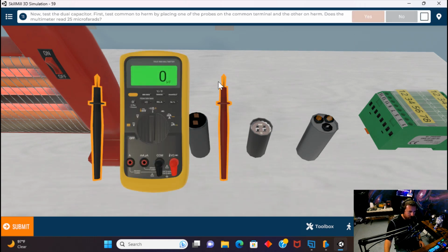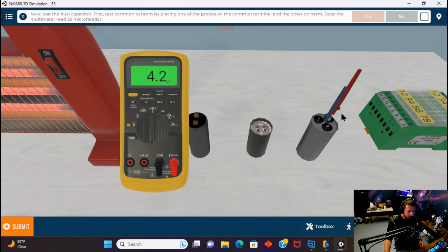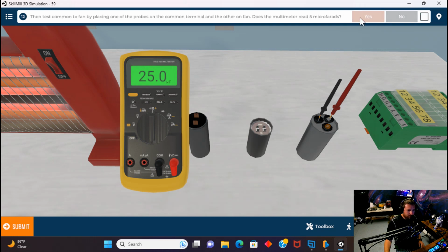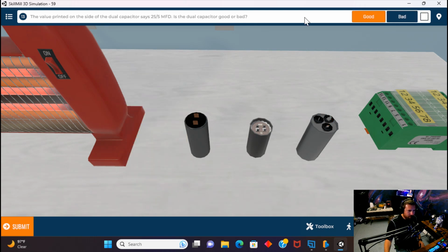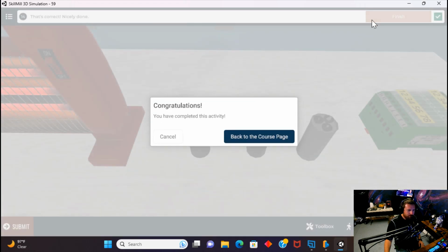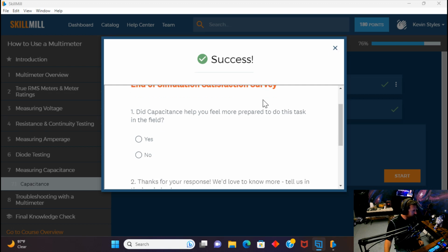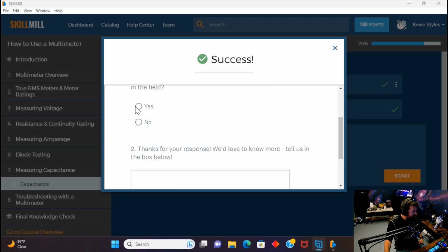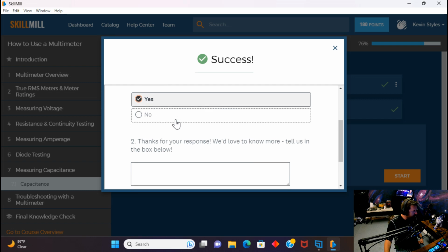That's what it says. Now it's telling you let's check the dual run capacitor. Does it read 25 microfarads on Herm? Yes. Test the common to fan by placing one of the probes on there. So now we need to put the probe onto here. Does it read 5 microfarads? Yes. It is a good capacitor. Finish. Congratulations. You've completed that part of the course. And it'll sometimes ask, did the capacitance help you feel more prepared to do this task in the field? Yes. Thank you for your response.